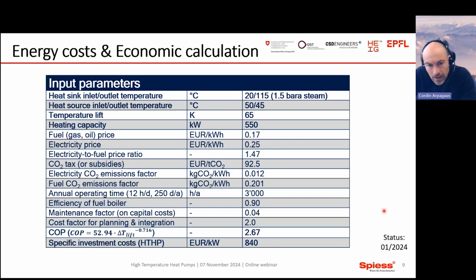So with that information, we can do a rough cost calculation. So we know the temperatures on the heat sink and on the source side, a temperature lift of 65. In that case, we assumed a heating capacity of the heat pump of 550 kilowatts. We had some information on the gas price and electricity price. So the electricity price was quite high, but also the gas price was quite high at that point. Today this gas price is much lower again. So this would make the case more difficult.